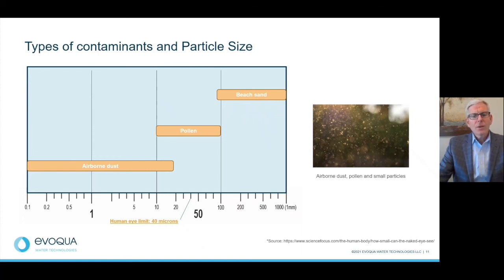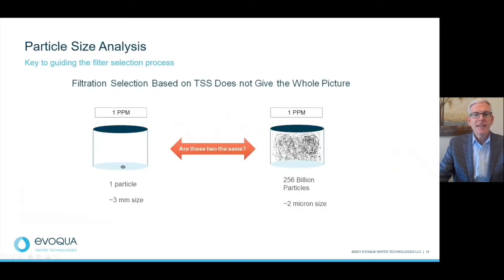I think we've all heard the question, what weighs more, a pound of bricks or a pound of feathers? And of course, they both weigh the same. A similar question is: is 1 ppm of TSS that consists of 1 3mm sized particle the same as 1 ppm TSS that consists of 256 billion particles that are roughly 2 microns in size? Now, while these are equal to one another in terms of the TSS they provide to the water, from a water treatment perspective, they are very different situations. And you can imagine it is much more challenging to remove the particles in the example to the right.